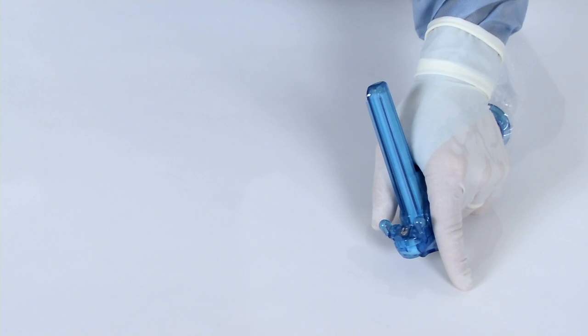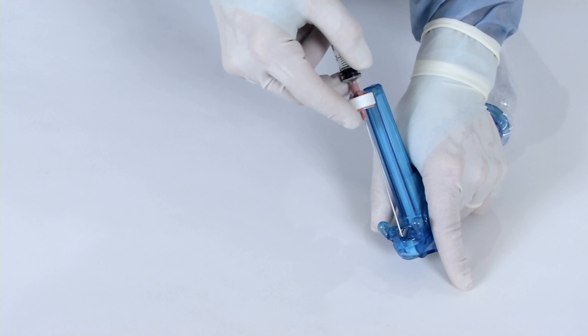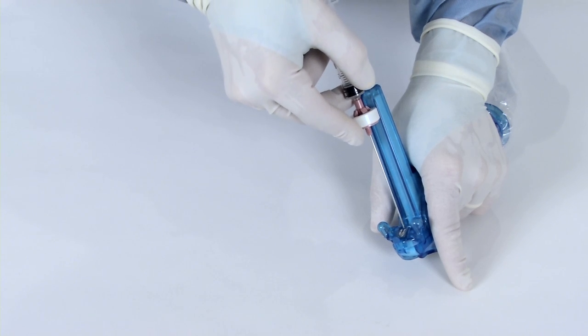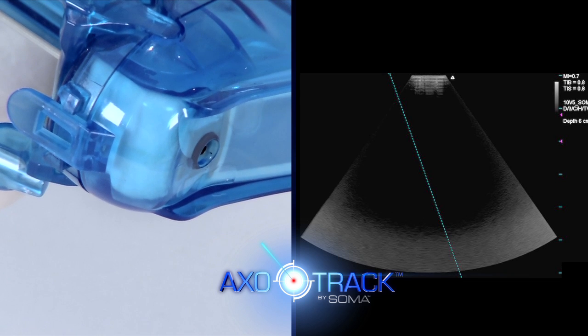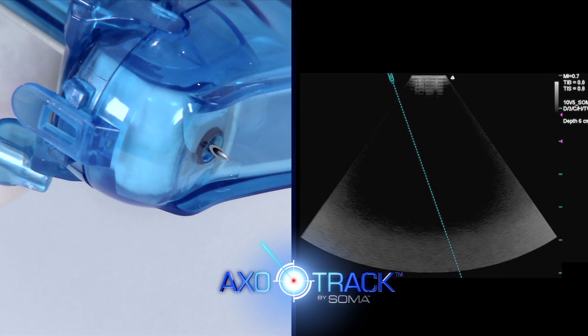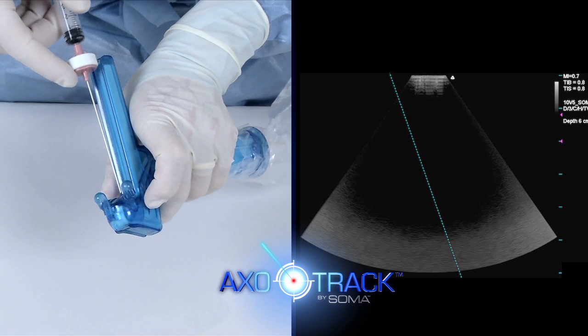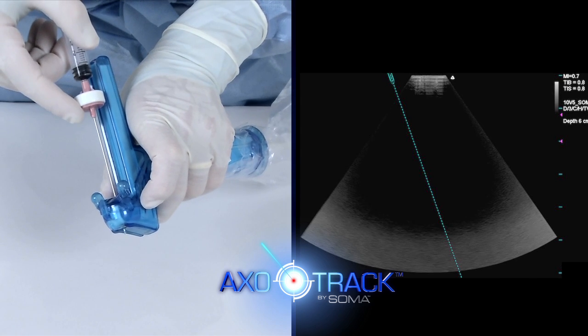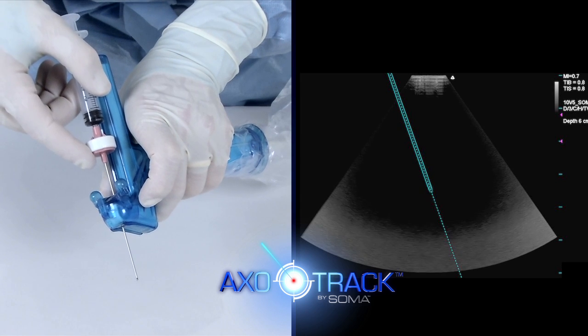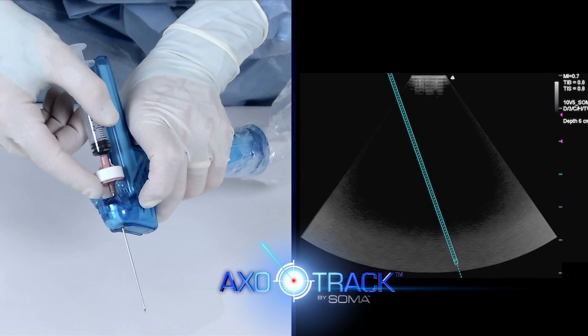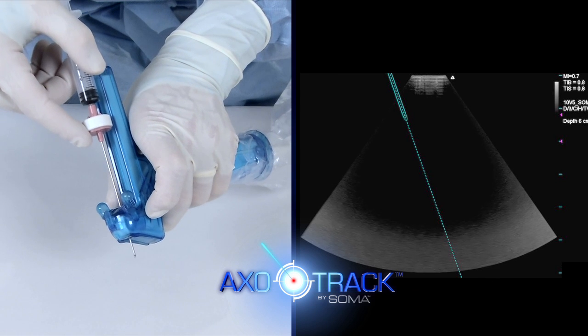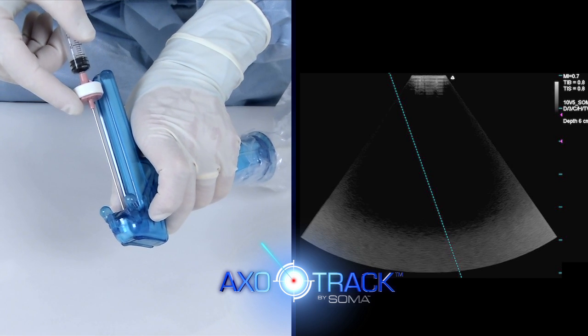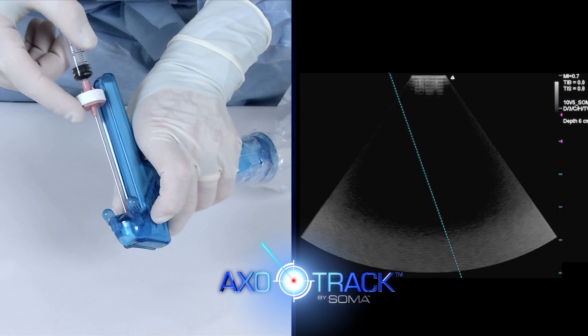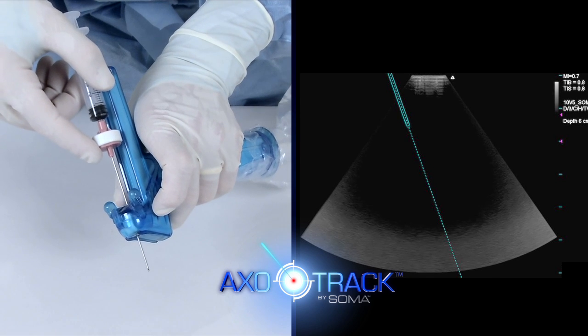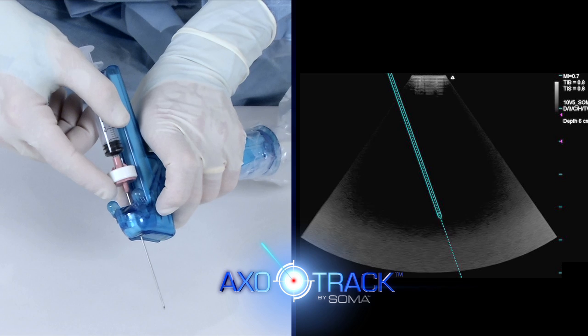As a final check before use, the practitioner passes the needle through the needle guide and observes when the needle tip starts to protrude from the bottom of the probe shield. At this point, the image of the virtual needle should be seen just entering the very top of the ultrasound field. This step assures calibration is correct. Finally, the practitioner slides the needle slowly back and forth through the needle guide and observes the virtual needle on the sonogram. The motion of the virtual needle should mirror the motion of the actual needle. If either of these system checks fails, the practitioner should stop the procedure and refer to the probe user guide.